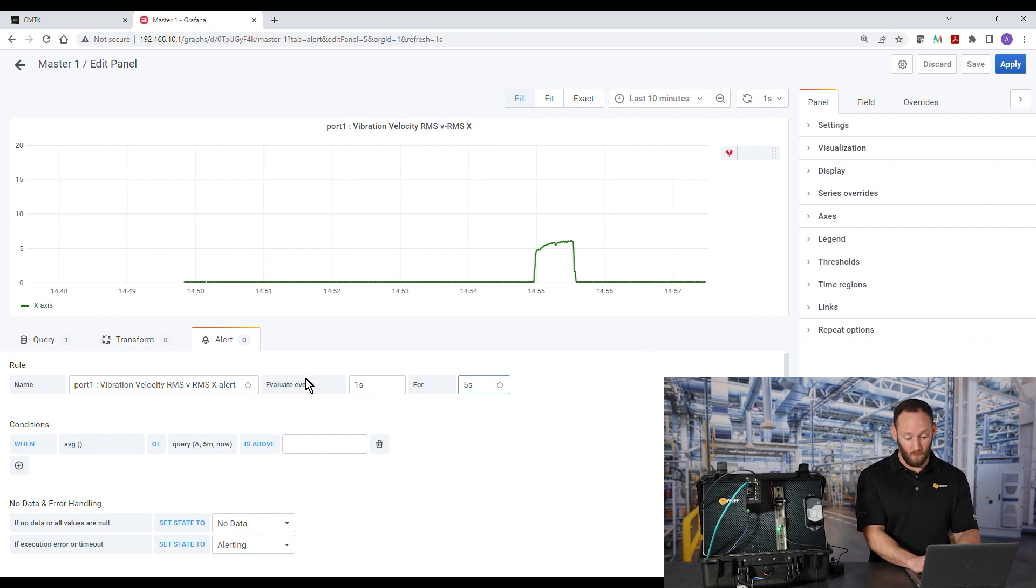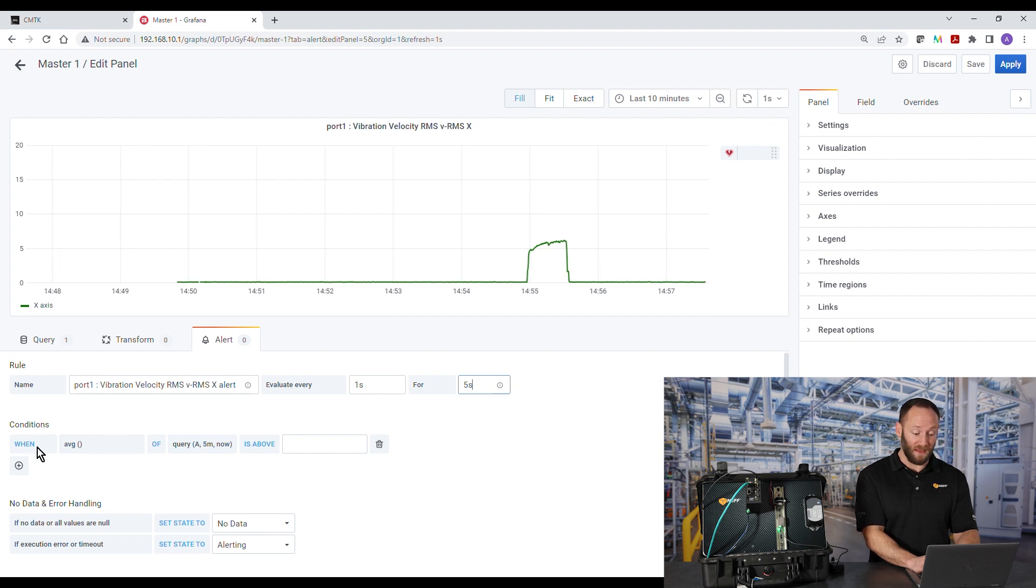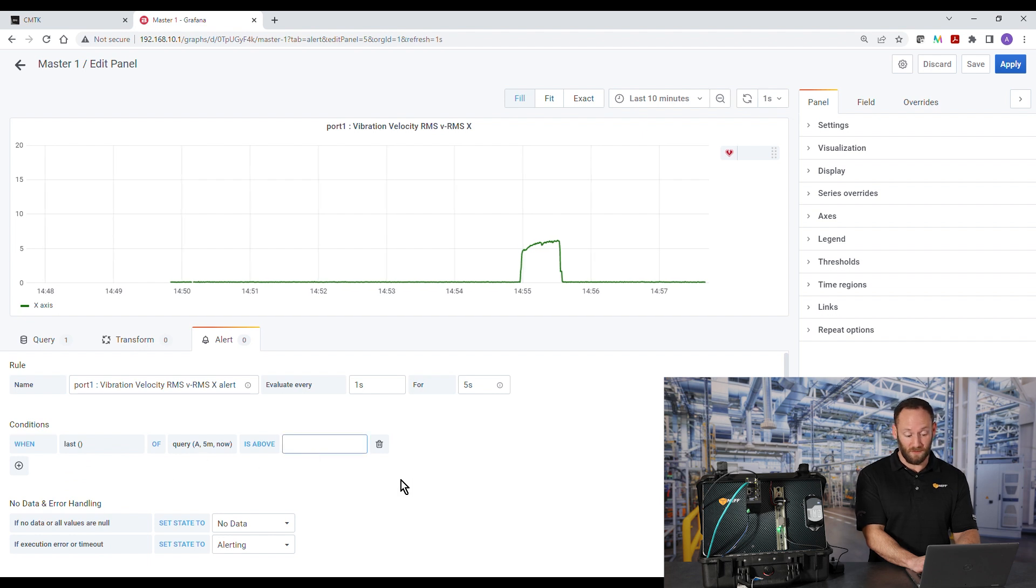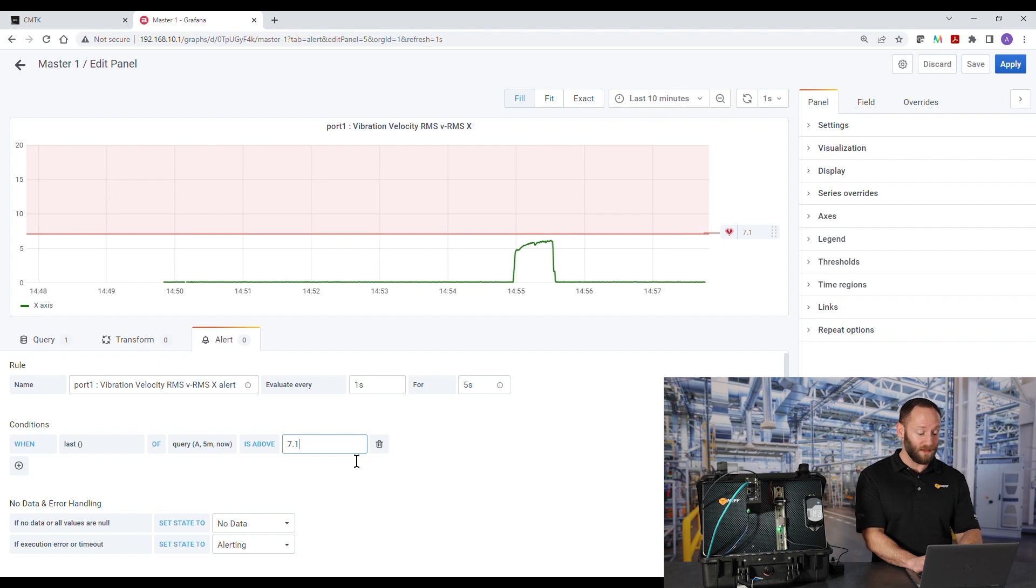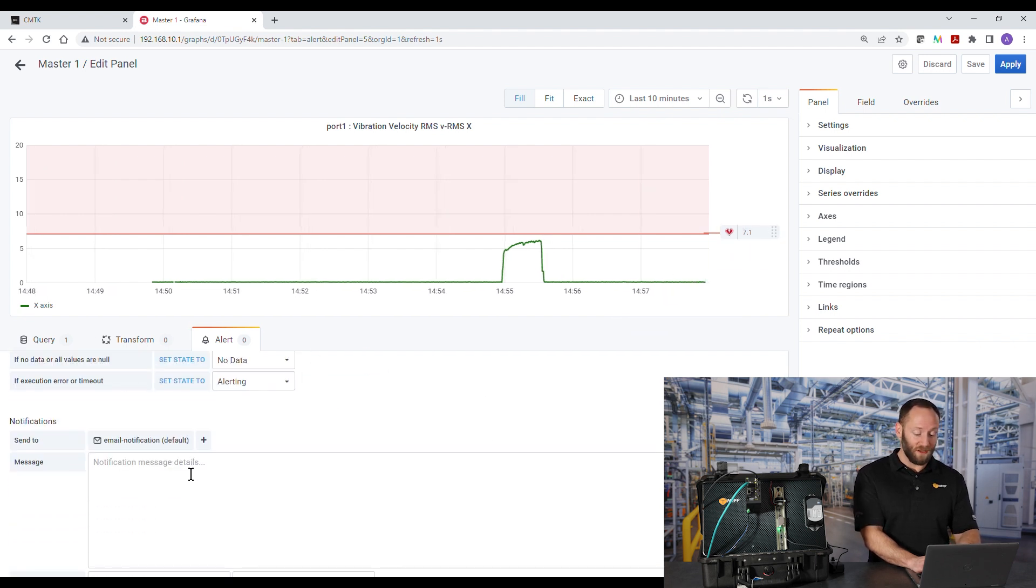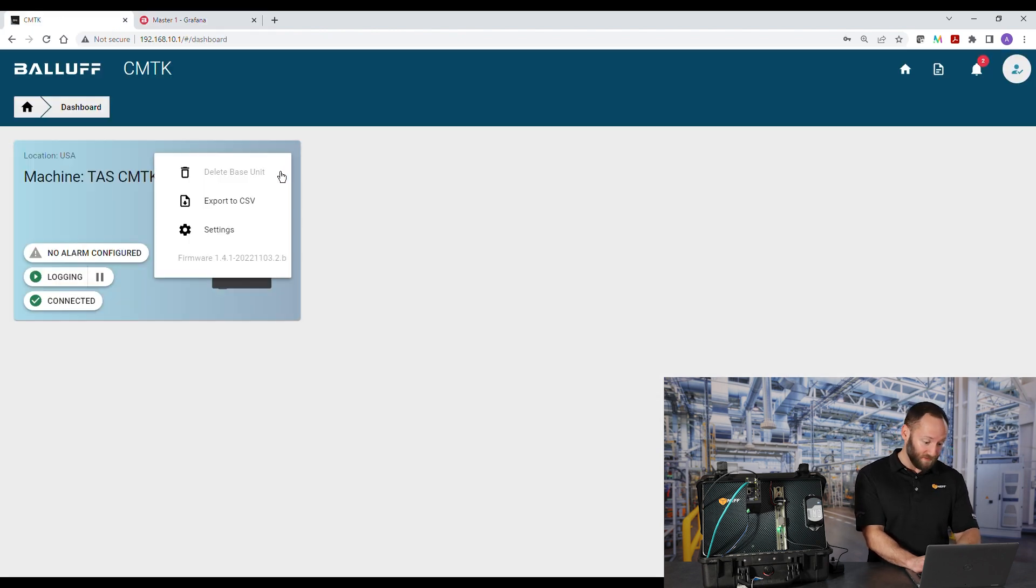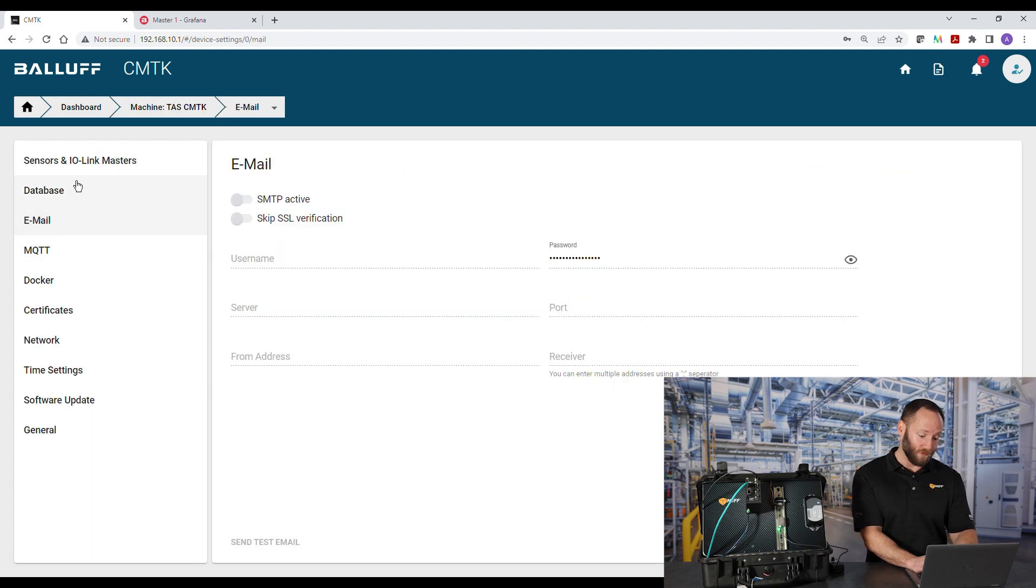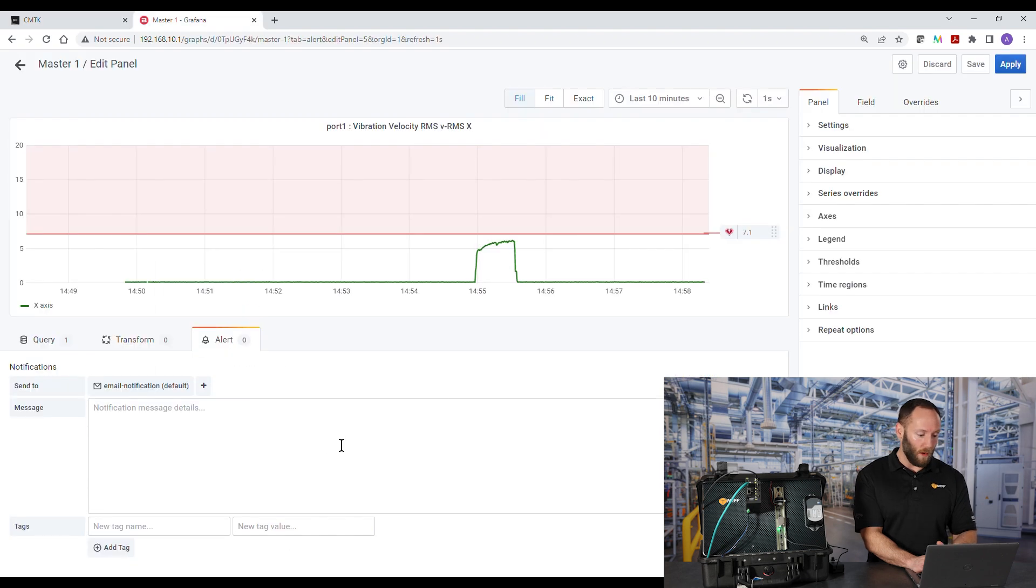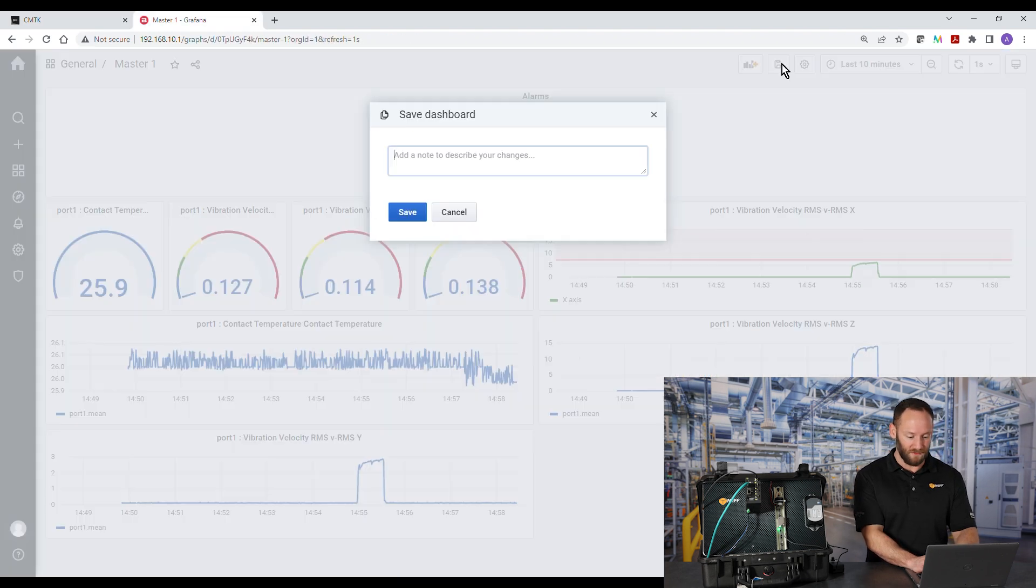After I set up that rule, I set up the condition for that rule. The condition is when. So instead of an average, we'll look at the last value and 7.1 millimeters per second, which is severity zone D. So anything above 7.1 millimeters per second, we'll send out an email alert. And this is where we could specify who gets the email as well as the body of the message. And hopefully this goes without saying, but the email server settings need to be configured correctly for the graphical interface to successfully send these emails.